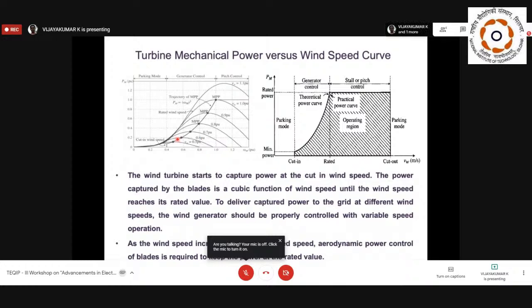Then you can substitute 0.6 per unit for this curve, 0.7 per unit for this curve, and 0.8 per unit, you'll get this curve, till 1 per unit of wind velocity, where you'll get this curve. Here the x-axis is the turbine speed, and the y-axis is the output power. Here we have considered steps of 0.1 per unit, but in practical conditions your wind velocity will keep on changing, so we'll get a number of same type of curves. For understanding purposes, we have considered the 0.1 per unit steps.